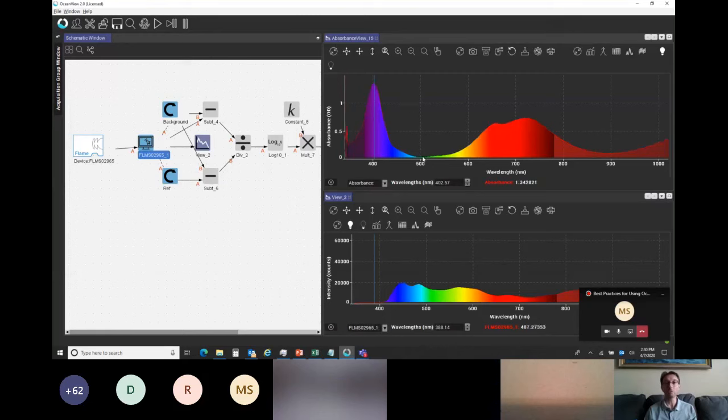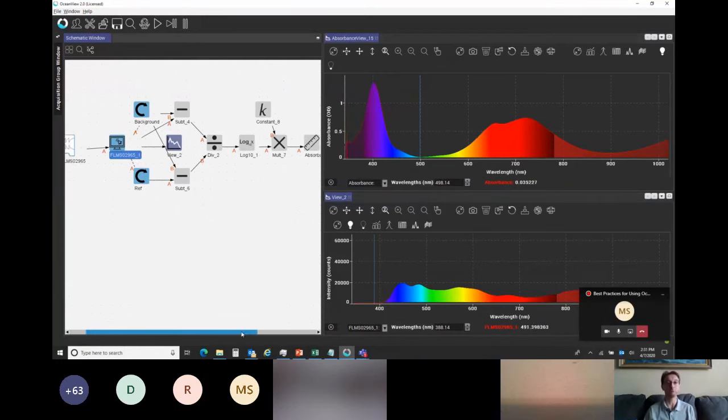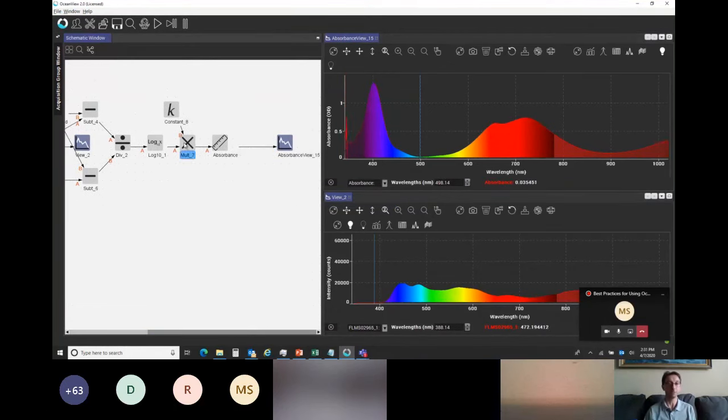The first thing to note is that there is a nice baseline region right at 500 nanometers. What we can do here is peg that to 0 because we don't want that to jump around. Notice if I move the cuvette around a little bit, you can see how by moving the cuvette, that moves around a bit. We don't want that to happen. So let's take a sub-range and peg that to 0.